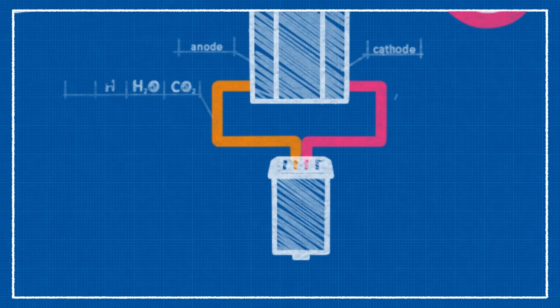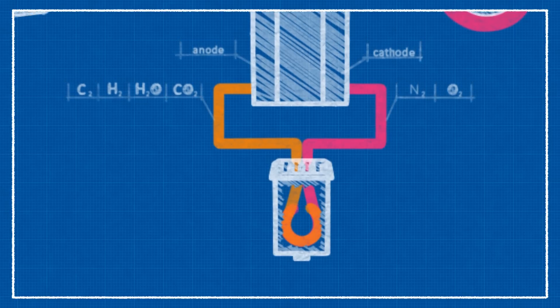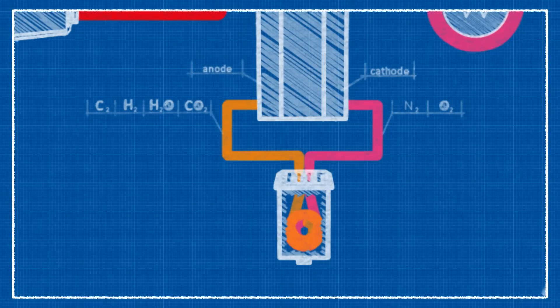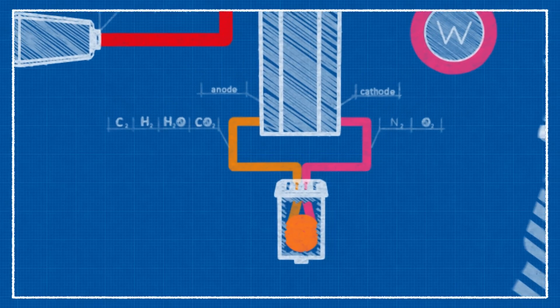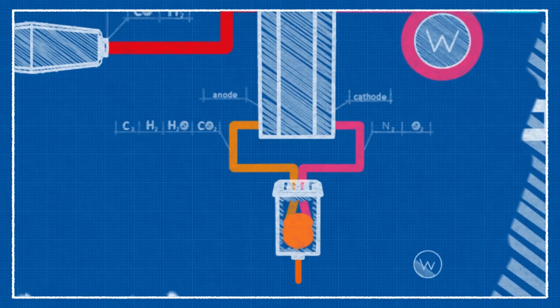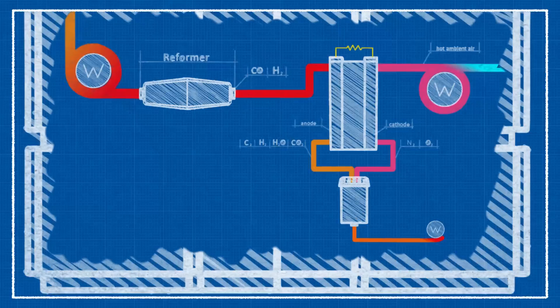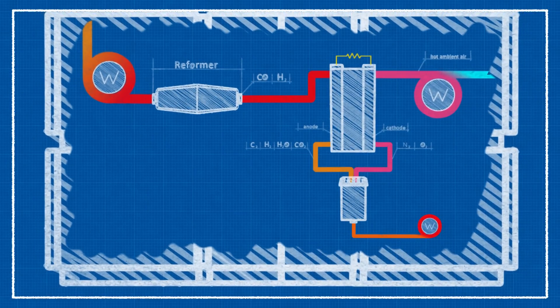These exhausts are mainly composed by carbon dioxide and steam. The two flows are mixed together in order to remove unreacted fuel and transform still available chemical energy in thermal energy. After preheating the fresh inlet streams, hot exhausts are available for thermal recovery in a gas-water heat exchanger.